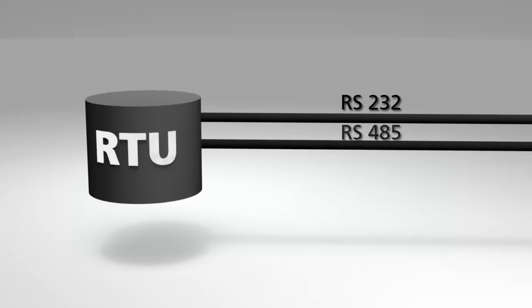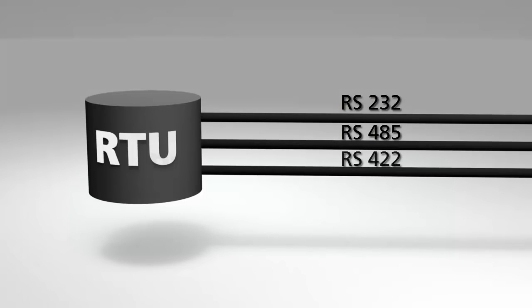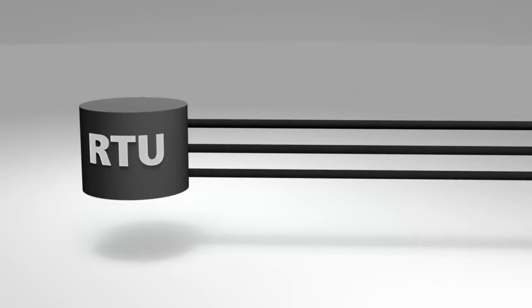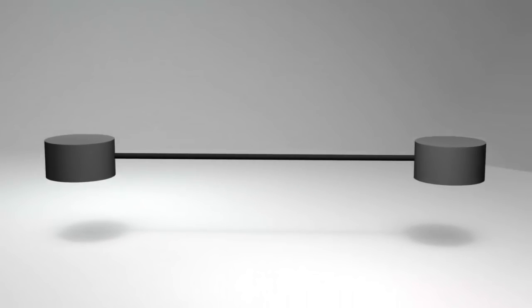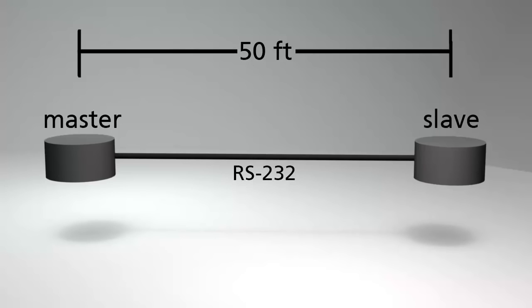Modbus RTU devices typically use one of three electrical interfaces: RS-232, RS-485, and RS-422. RS-232 is a simple point-to-point arrangement. If you only need to connect one device to another and the distance between the two devices is less than 50 feet or 15 meters, then RS-232 will do the job.